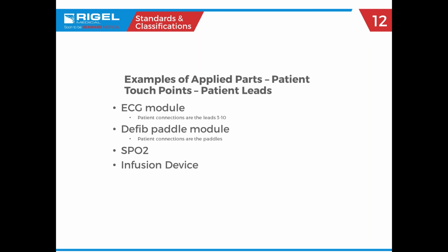Okay, so when doing electrical safety testing, you're also going to have to test the applied parts for leakage as well. Some examples of this would be an EKG box, where the patient connections would be the leads, a defib box, where the patient connections would be the paddles, and it could also be an SpO2 attachment or even an infusion pump, where you would be testing the connections to the patient for leakage.